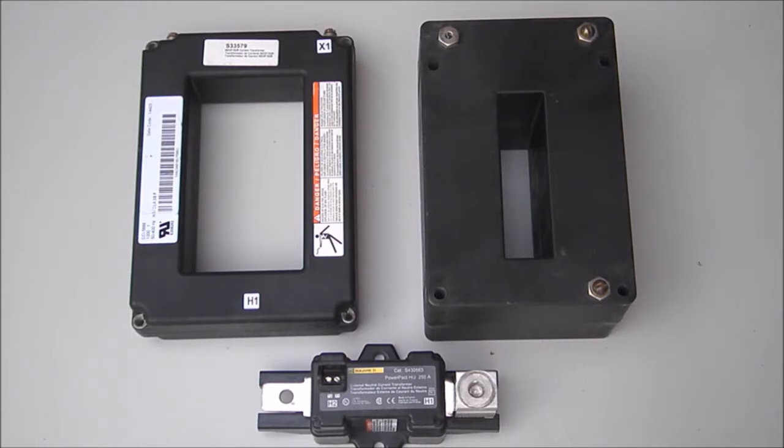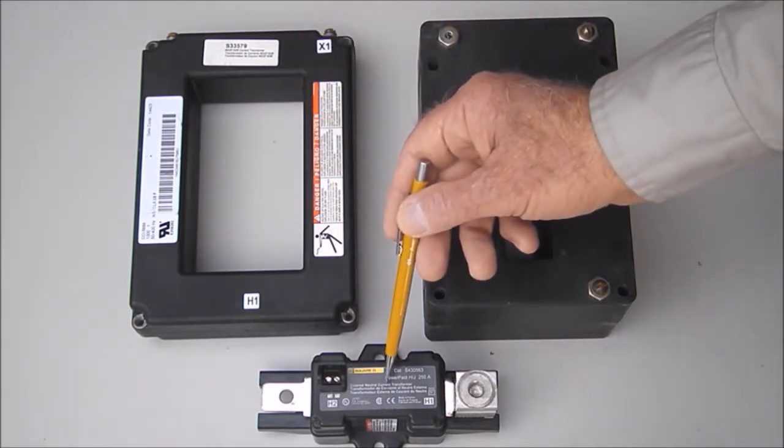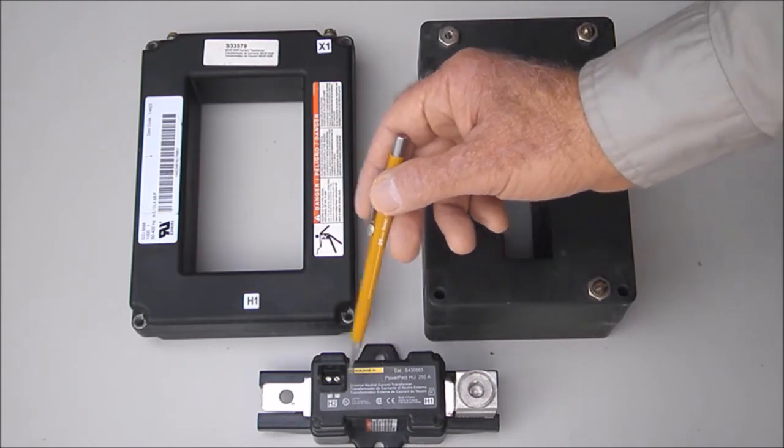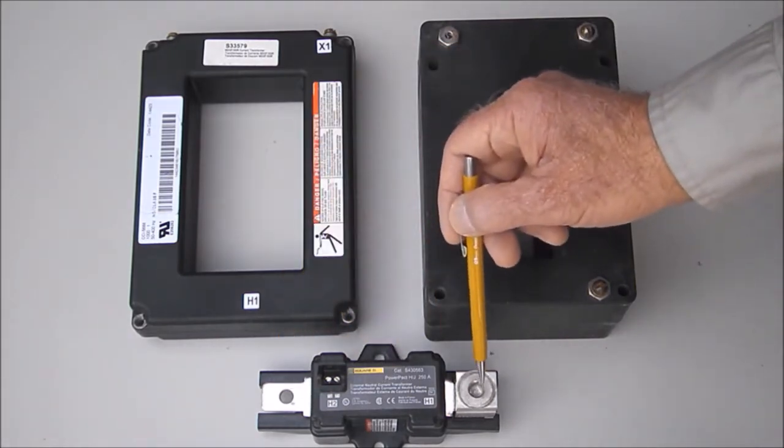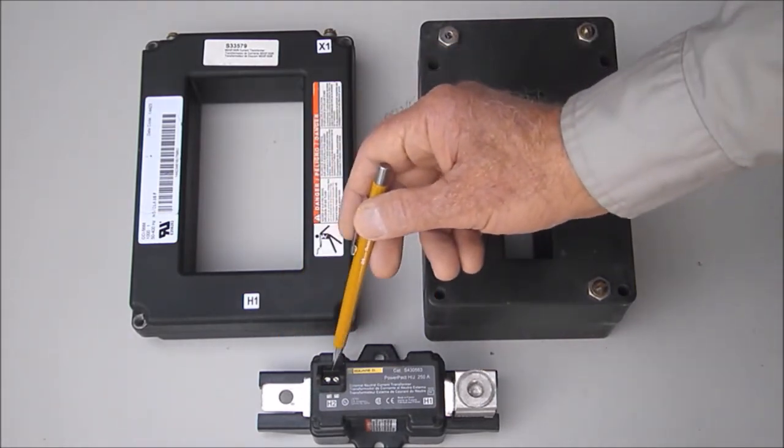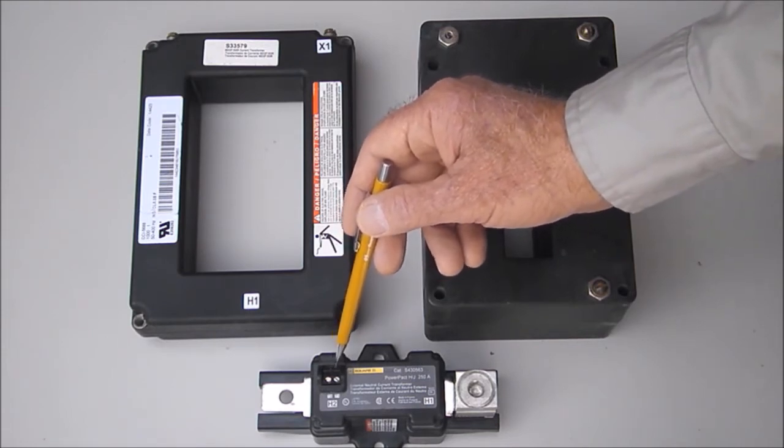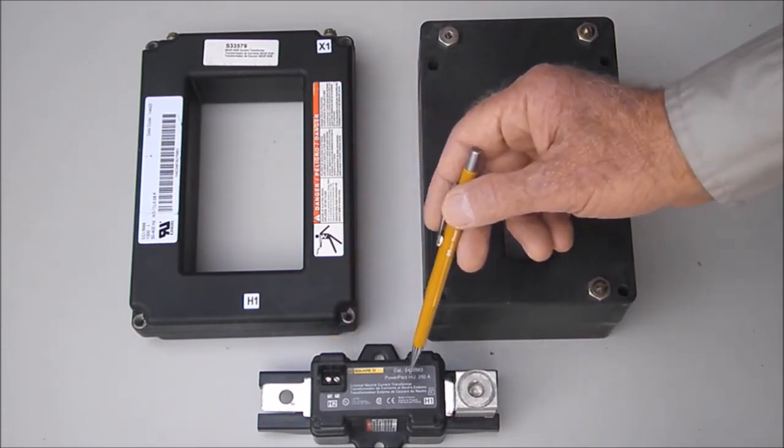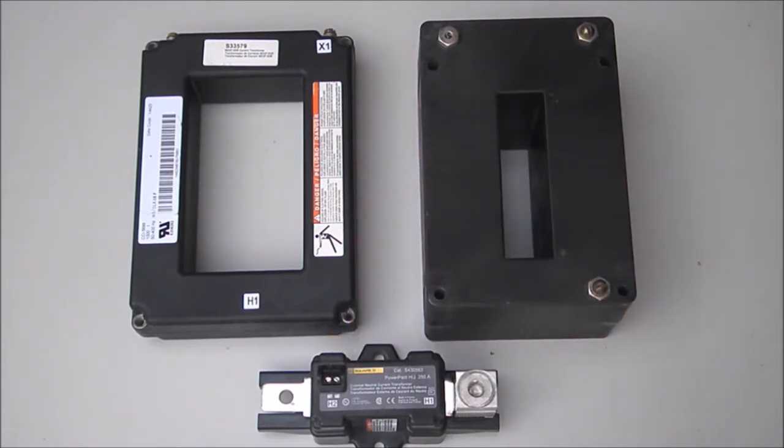Shown here are several types of neutral current transformers. This small one is a standalone bar type bolted in series with a neutral circuit. This NCT will report neutral current information from these two terminals to electronic circuit breaker or ground fault system electronics.